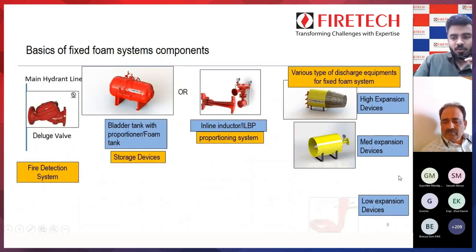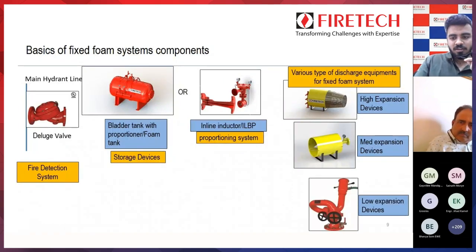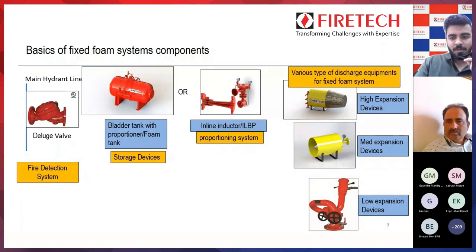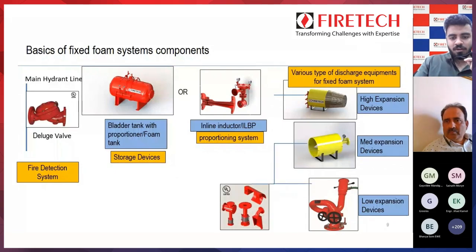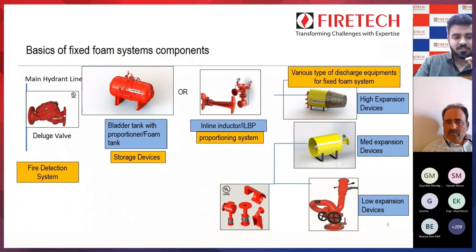Third is the low expansion devices — your foam monitors, that is water-foam monitors, which are used for secondary fire protection. Your foam chambers or makers are used for storage tank protection as primary devices. So detection device, storage device, proportioning device, and discharge devices — these are the four types of devices required for your fixed foam system.